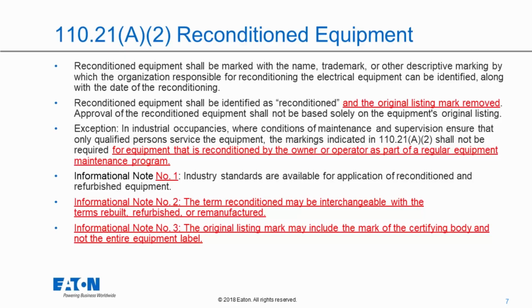So again, what we're talking about is it's not uncommon for an industrial facility to have equipment that perhaps is no longer operational, and they will bring that back to operation as part of their normal maintenance program. So that would not be considered reconditioned. If they're doing the work, they do not have to remove the original listing label and identify it as reconditioned. They also added two informational notes. One is about industry standards available for application of reconditioned and refurbished equipment. So there are standards like PEARL that do provide some guidance for that.